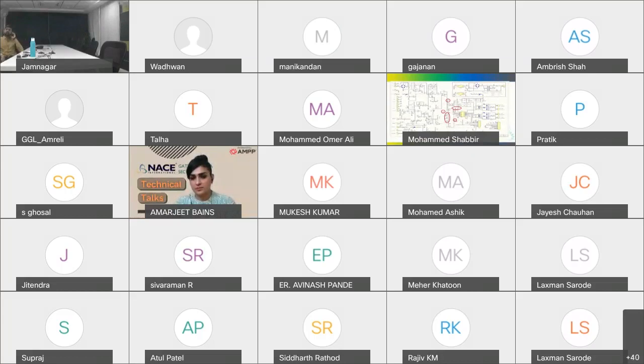Without this type of electronic circuit information, we have to simply wait on the OEM or talk to various manufacturers. If the repairing manufacturer is different from the original rectifier manufacturer, there will be issues of mechanical fitment. In the end, it's the end user who suffers, waiting for the rectifier to be up and running. So where we feel we have no option other than going electronic control, this is the type of schematic we should demand from the manufacturer.